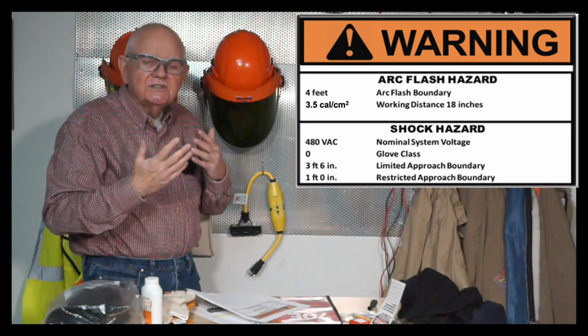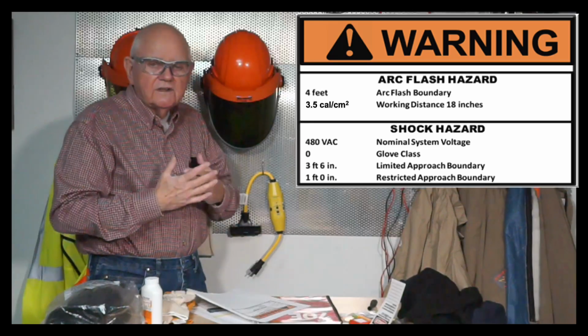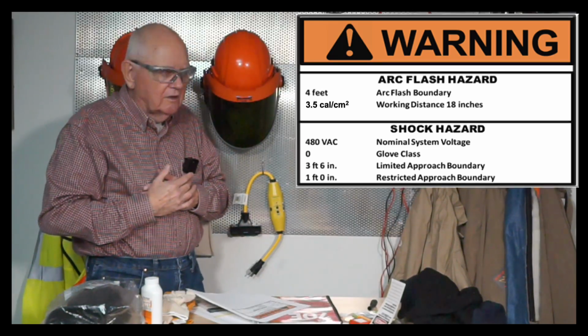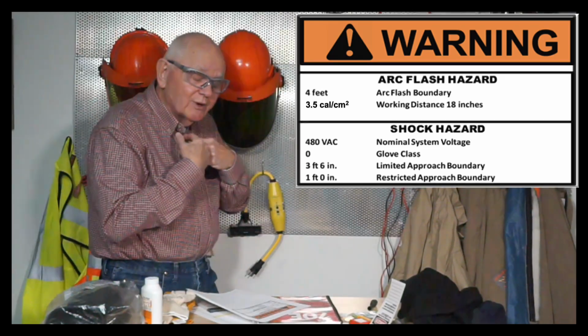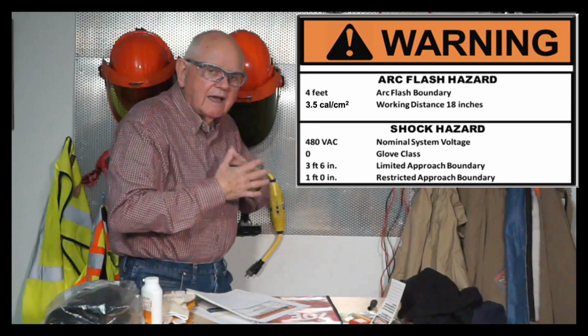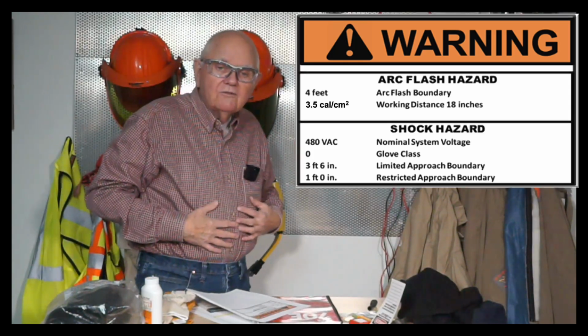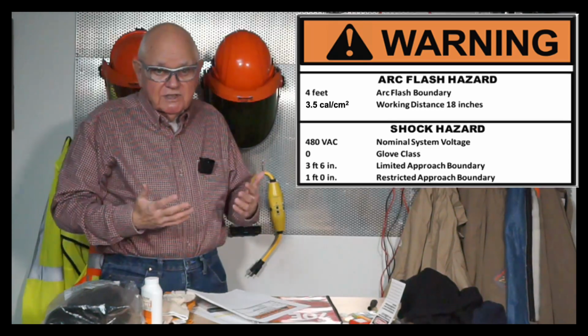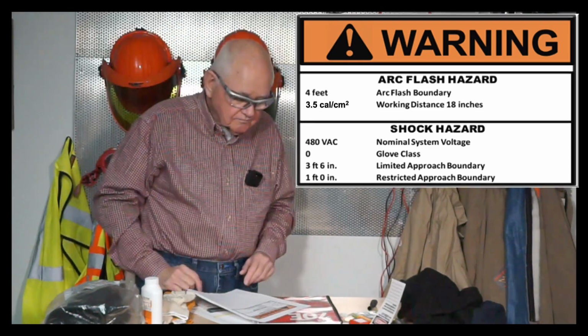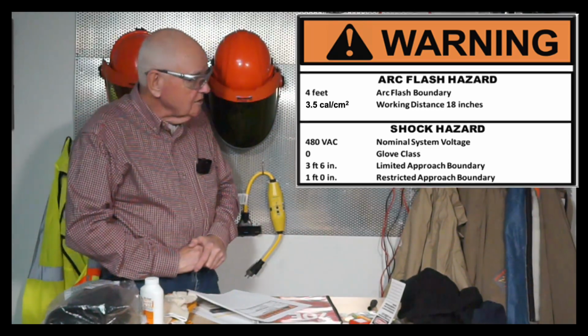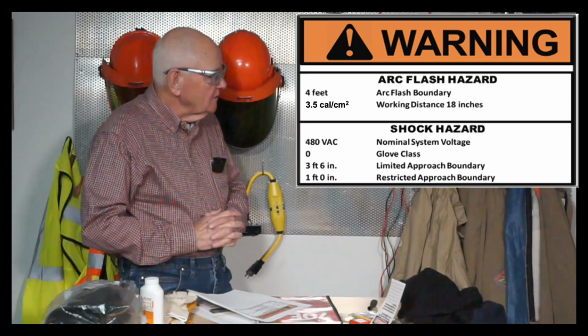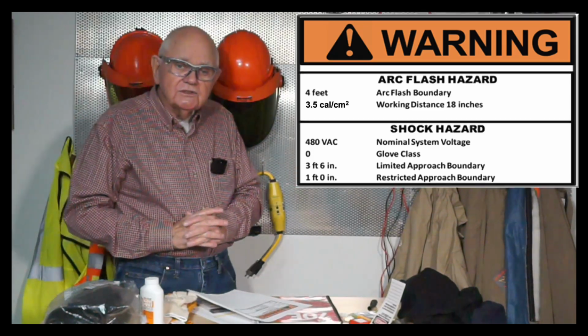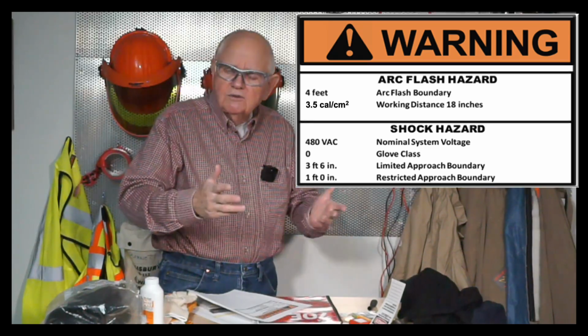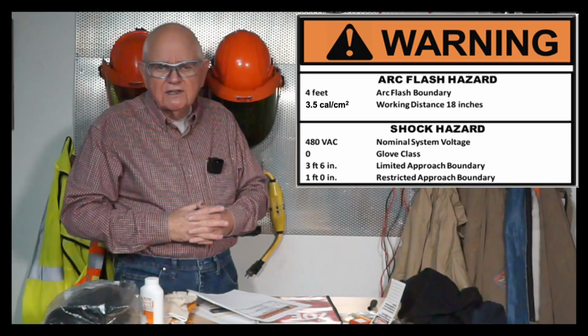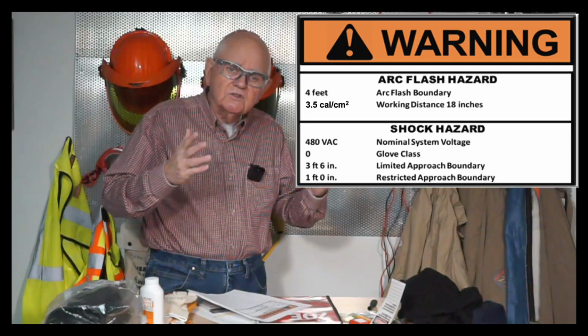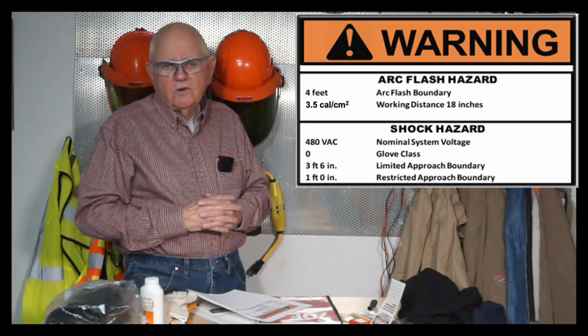NFPA 70E is designed to make sure that I don't get anything worse than a second-degree burn, because a second-degree burn will heal. So if I were to go any closer than that arc flash boundary, I better have on the appropriately rated PPE in order to protect me from that arc flash. Now, it says 3.5 calories per square centimeter at a working distance of 18 inches. The working distance is typically 18 inches for the equipment we troubleshoot, such as MCCs, control panels, and disconnects, 24 inches for switchgear, and 36 inches typically for medium voltage equipment.